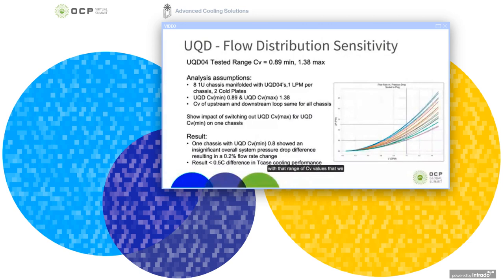Now, along with that range of CV values that we determined, you can see the graph on the right showing the CV values or pressure delta P curve. And you can see that as the flow gets larger, the spread of the delta P range gets wider. So we've done a lot of analysis and some sensitivity testing, in the range of the UQD values that we tested, the lower range of 0.89 all the way up to the maximum range of 1.38.